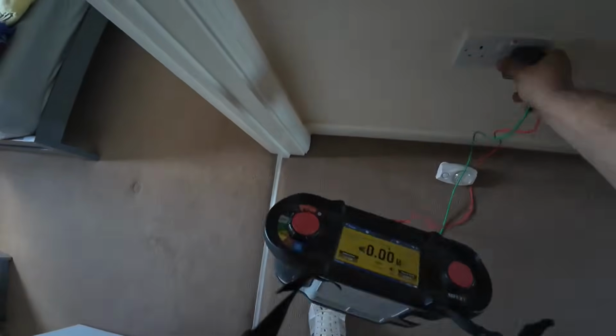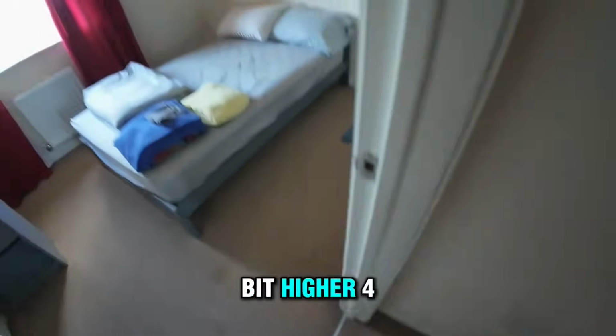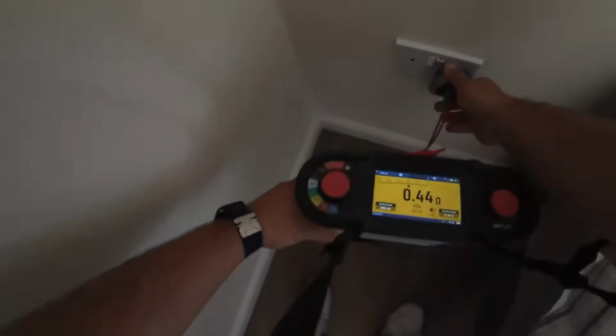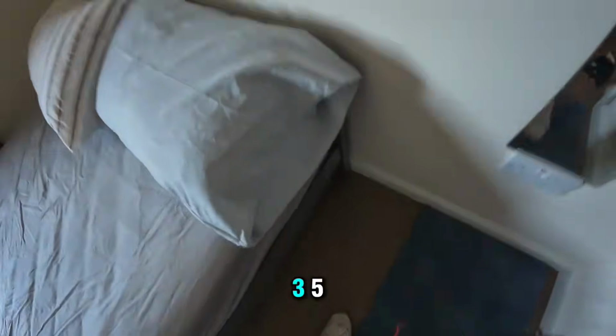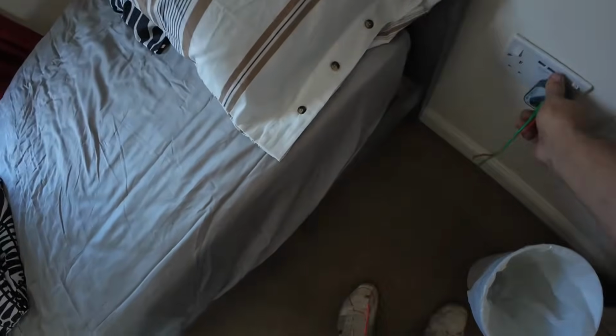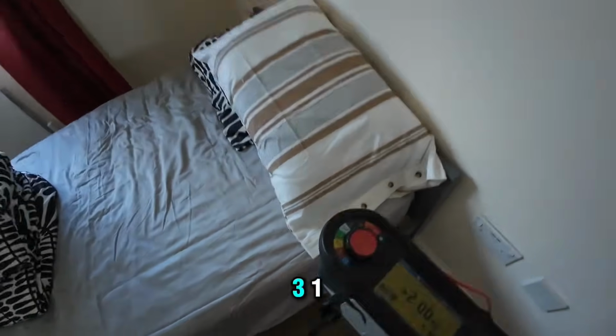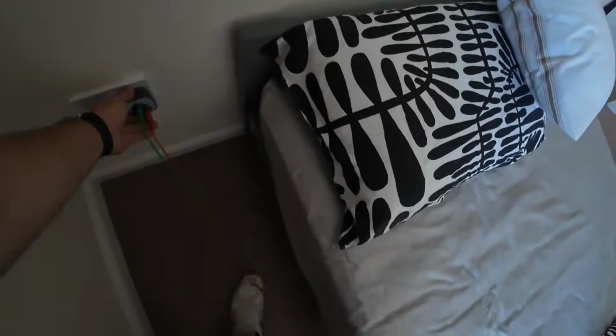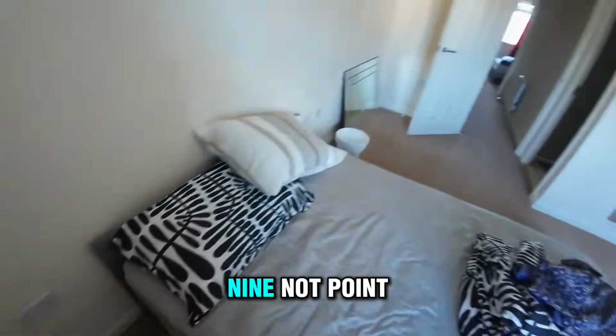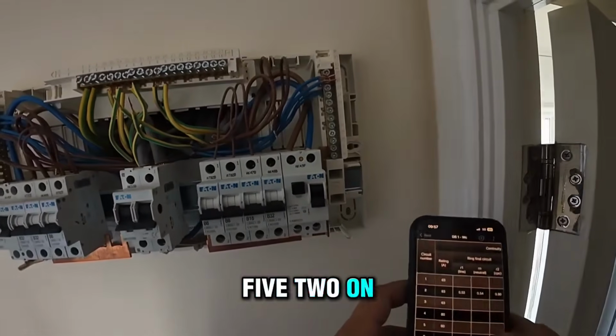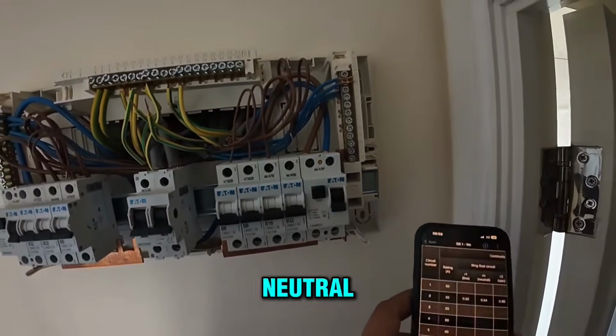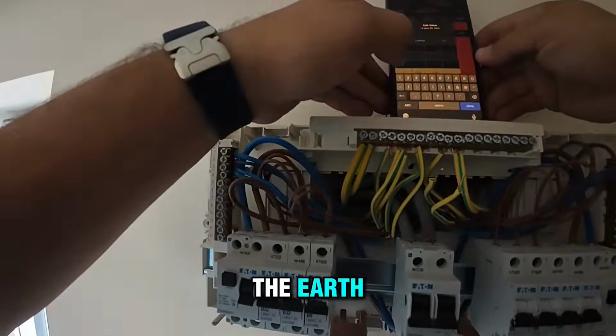0.30. Lights. That's a bit higher. 4.3. 4.4. 3.5. 6.1, that's the spur. 3.1. 0.29. 0.52 on live, 0.54 on the neutral, but nothing on the earth.